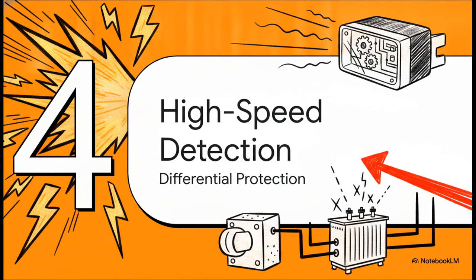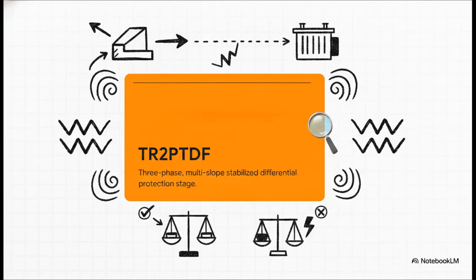Okay, so how do we catch this in time? Section 4, high-speed detection. Enter differential protection. In plain English, this protection stage has one primary job: compare the current entering the protected zone with the current leaving it. If there's an unexplained imbalance, it means there's an internal fault, and it trips. Differential protection is hands down the fastest and most selective way to detect these issues because it completely ignores harmless external surges or faults outside of its zone. It is looking purely at the health of the generator transformer block itself.